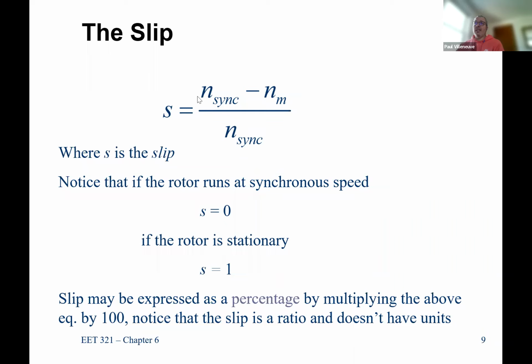We actually have more than these two extremes, but if it's running as a motor, we'll pretty much have these two values here. What happens when the slip is 0? When S equals 0? How would you describe something that has a slip of 0? What's another way to say a slip of 0? Things aren't moving relative to one another. Yeah, it's not slipping. It doesn't slip. So it's running at synchronous speed, if it's possible. So if slip equals 0, it runs at synchronous speed.